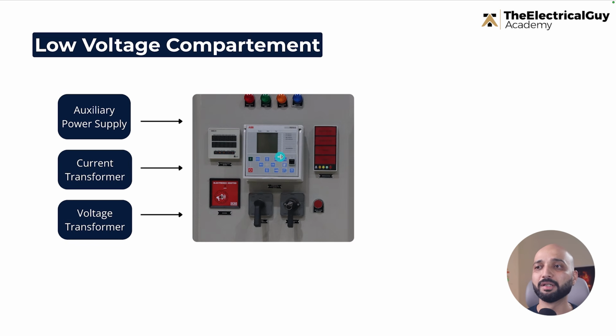The second input is the current transformer. We can also have relays which operate based on the value of current. There will be meters, and for all that, the current transformer is the input. Now the current transformer can accept, let's say, 800 ampere coming from the incoming. That 800 ampere will be stepped down to, let's say, 1 ampere, and then that 1 ampere goes inside the meter, and the meter gives us the reading, right?